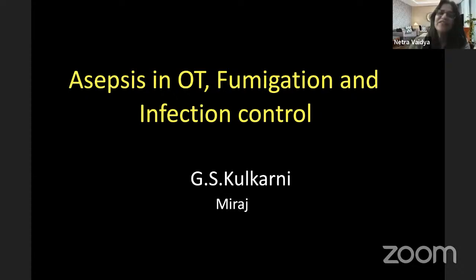Anytime, the square tray is better, which has holes in it, so that your steam penetration and your air removal is easy. With a drum, there are chances of getting wet packs, and even if you are going to use drums, you need to also give importance to the mass you are going to put into it, and use it only one time and not repeatedly, because once you open it, it's going to become unsterile. So the preferred method is tray. Tray. I use a tray, that aluminum tray, and I cover it with linen.